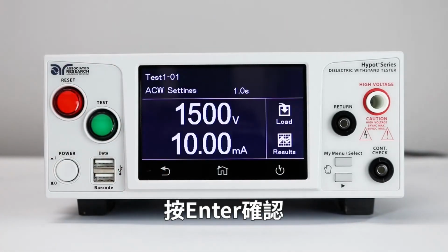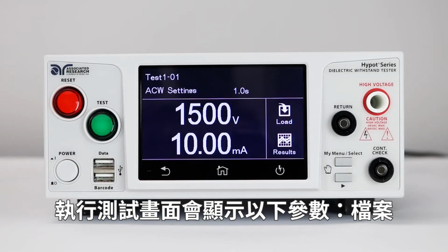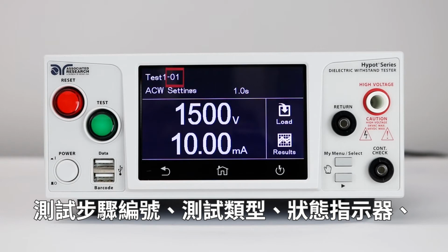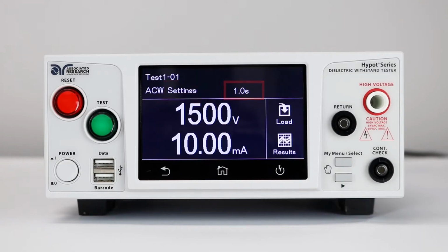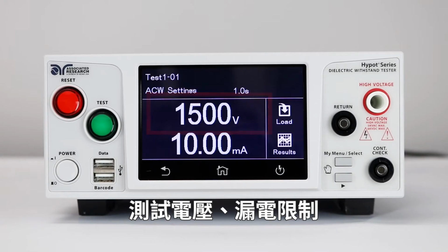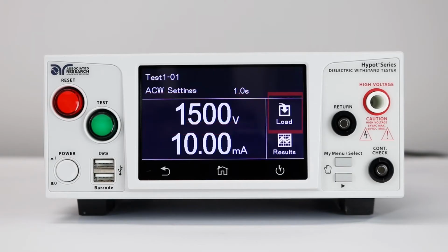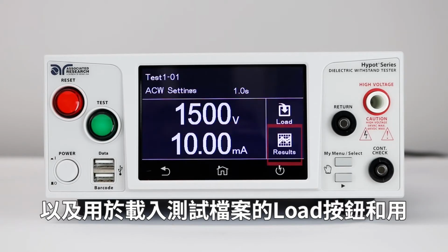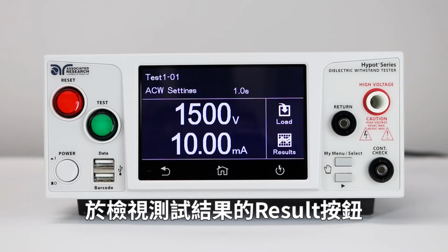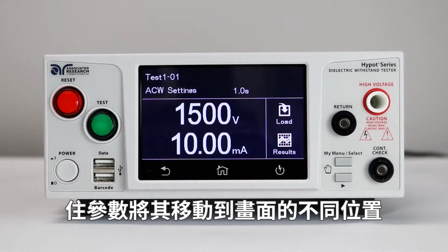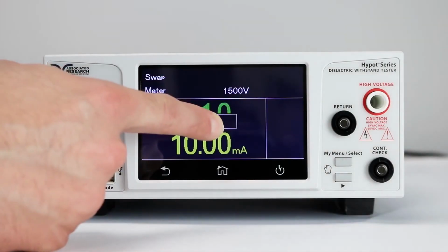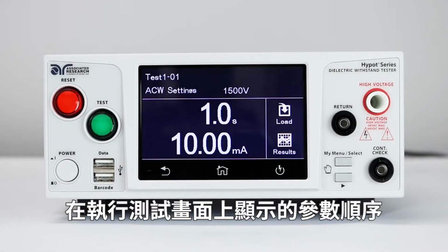Press Enter to confirm. The Perform Test screen displays the following parameters: file name, test step number, test type, status indicator, test time, test voltage, leakage limit, and load button for loading test files, and results button for viewing test results. You could also press and hold a parameter to move it to a different portion of the screen. This allows you to customize the order of the displayed parameters on your Perform Test screen.